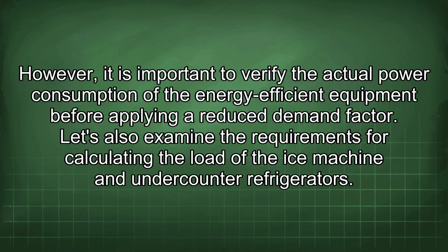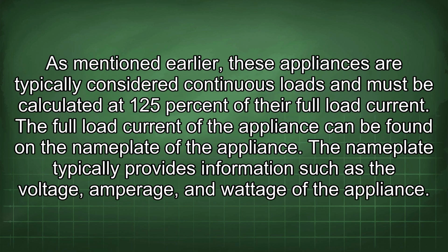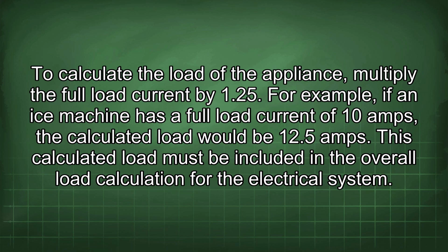Let's also examine the requirements for calculating the load of the ice machine and under-counter refrigerators. As mentioned earlier, these appliances are typically considered continuous loads and must be calculated at 125% of their full load current. The full load current of the appliance can be found on the nameplate. The nameplate typically provides information such as the voltage, amperage, and wattage of the appliance. To calculate the load of the appliance, multiply the full load current by 1.25.